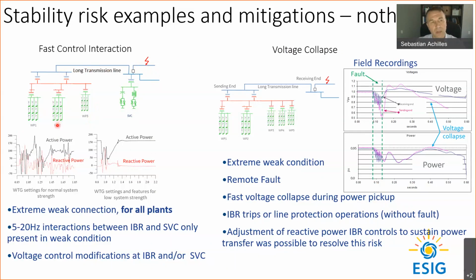If you have wind plant 1 and 2, and you add wind plant 3, the extreme weak condition applies to everybody, not only the last plant connected. So this particular condition means the cluster of three inverter-based resources sees an extremely weak condition.